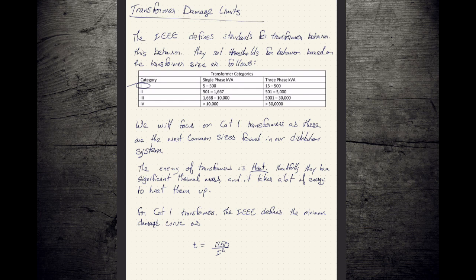And so the other thing that is happening here, other than heat, and thankfully our transformers are these bulky things made out of steel, so it's going to take more than a little bit of heat to actually warm the thing up, which in this case works greatly to our benefit. But the other thing that happens under high current flow conditions, and this is more of a problem under faults than it is under inrush, is that as the current goes up, the magnetic forces also go up. And so you get this force, and it's literally the coils start squeezing around the core. And if they're not properly braced, the coil itself will literally crush down on the insulation that protects it, and the transformer can crush itself to death.